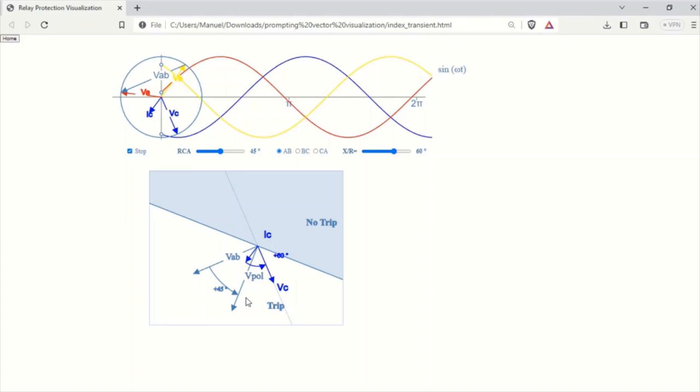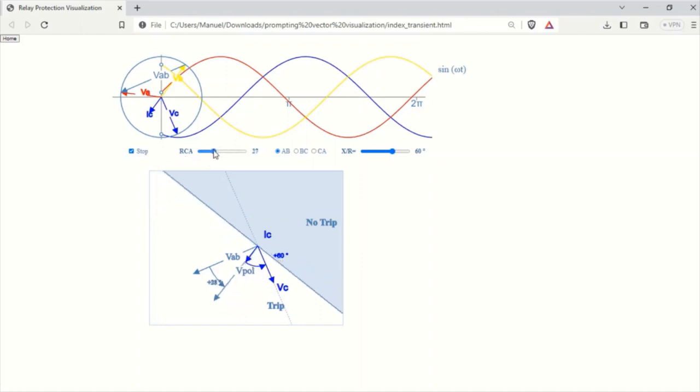This voltage vector labeled VPOL is what the relay uses to make a trip decision. In our visualization, this is labeled as RCA, which stands for Relay Characteristic Angle. I have included an input field that allows you to change this value with a slider.